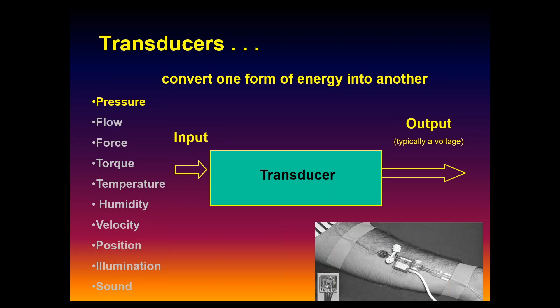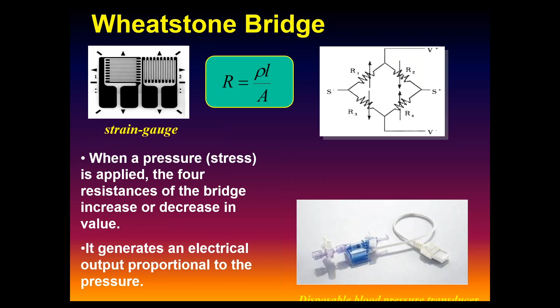Fundamentally, what's going on in these semiconductor devices is essentially resistive strain gauges of sorts. When pressure is applied, some of the older devices had almost like a diving board cantilever design, where they had a piece of silicon with two resistors etched on the top of the board and two on the bottom. The pressure applied at the end of the diving board changes the length and the area of the strain element, like pulling on a piece of taffy. You know, the length changes and the area gets smaller. Combined, those changes in resistance produce a voltage change. So fundamentally, they work really slick that way.